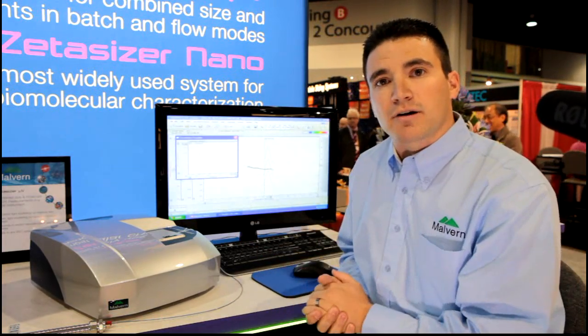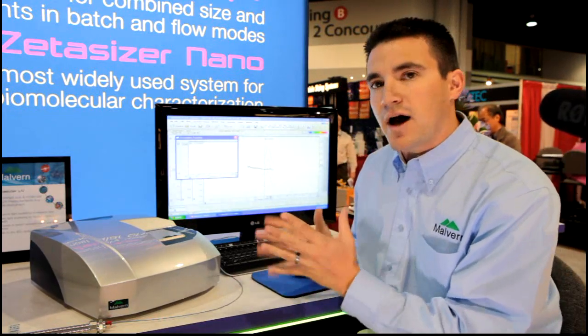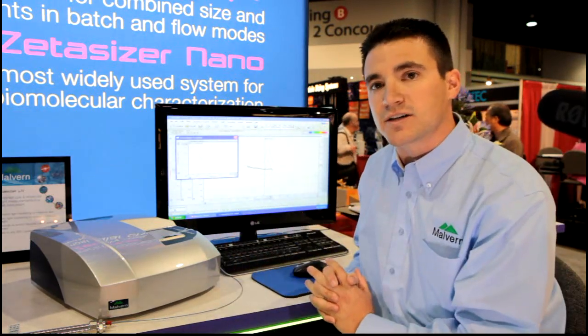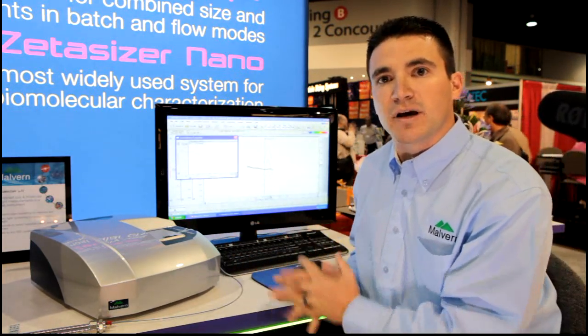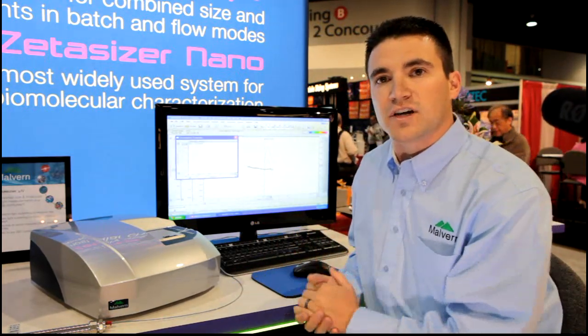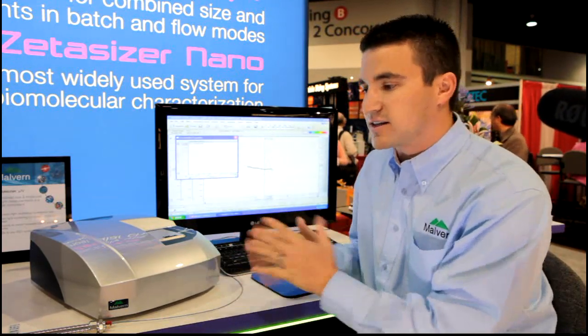The flow cell is 8 microliters, so you maintain the resolution of your chromatography. This is really a one-box solution to protein characterization that can be added to a current Malvern Viscotek system or any HPLC system, and has the capabilities of bringing in external refractive index and UV signals into the software so that you don't need to add any additional detectors other than this single box.